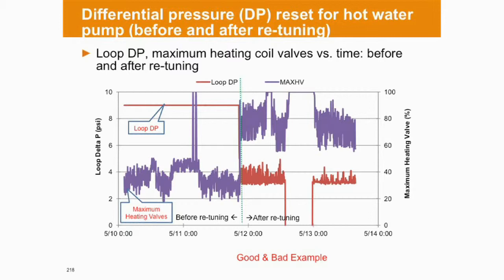So there's an opportunity to say, you know what, I don't need 9 PSI. I could have it automatically reset. And you see that before and after as you move from left to right on this chart. The DP set point dropped significantly from 9 down to about 4, maybe as low as 3. I'm not sure what happened there on the 13th, Friday the 13th, something went bad. But anyway, you can see the difference. And so we're dropping the DP, the loop set point, saving some pumping energy, and getting the valves to go a little more wide open, avoiding issues with wire draw.